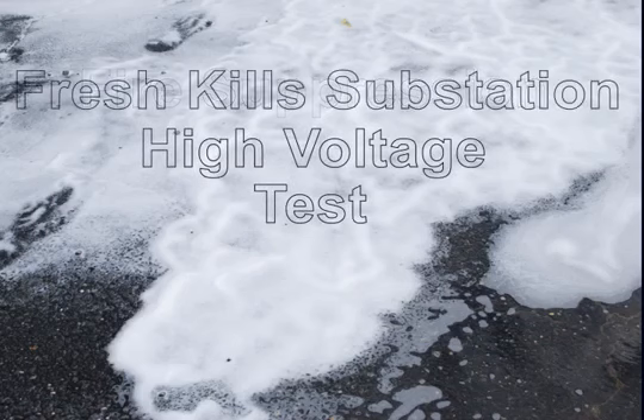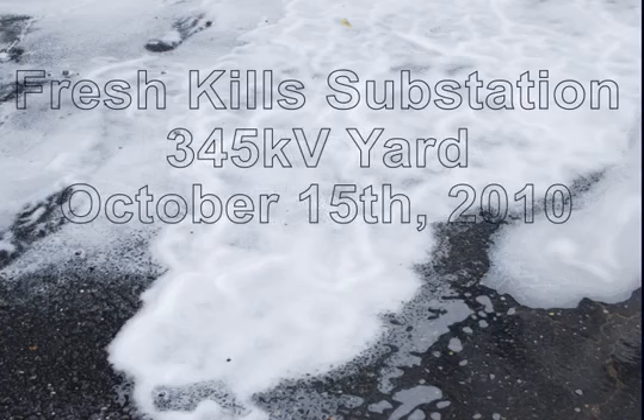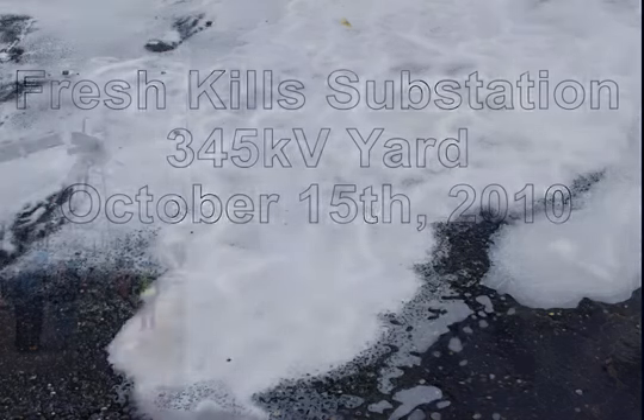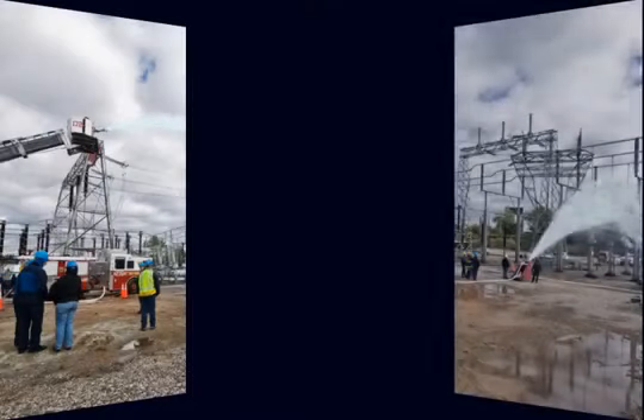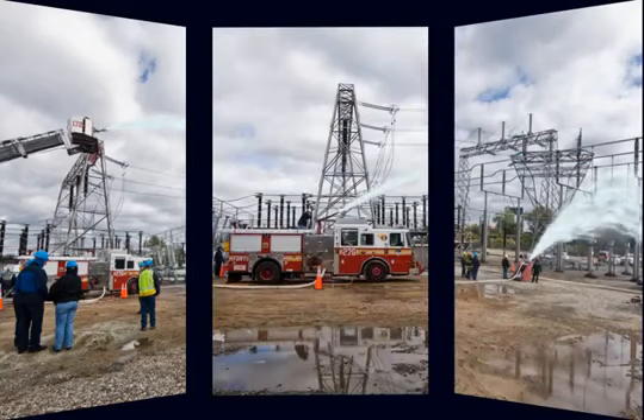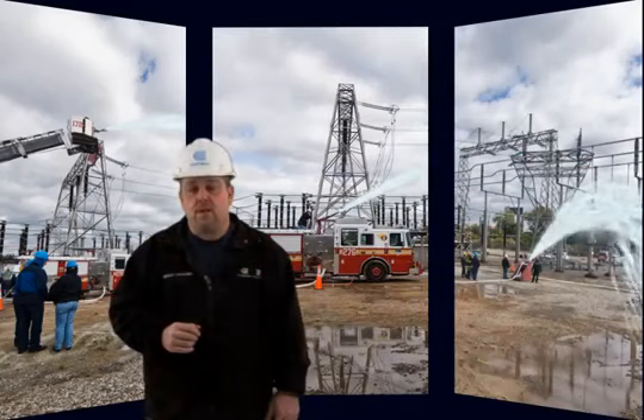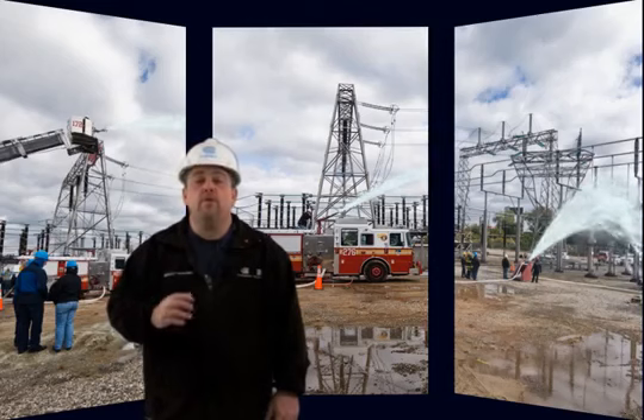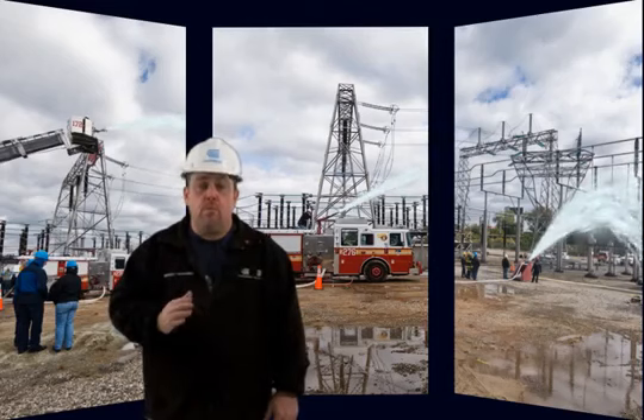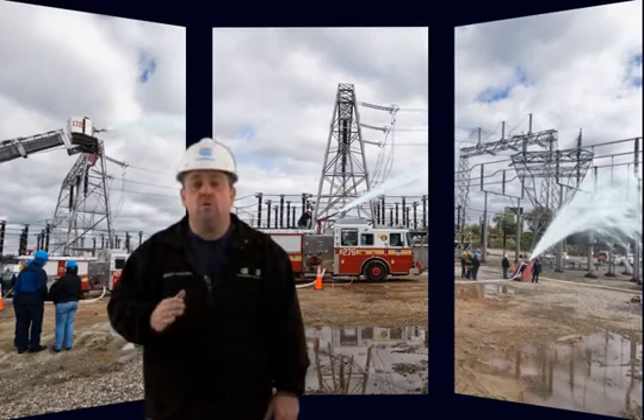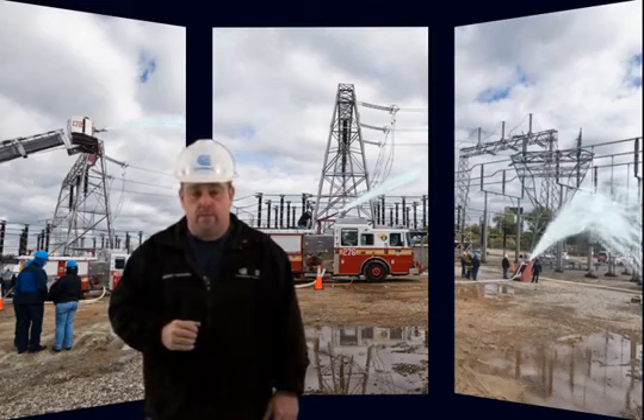On October 15, 2010, Con Edison and the FDNY conducted a live suppression test at the Fresh Kills 345,000 volt substation. The purpose of the test was to measure leakage current from the high voltage conductors back through the suppression agent to the fire department apparatus.